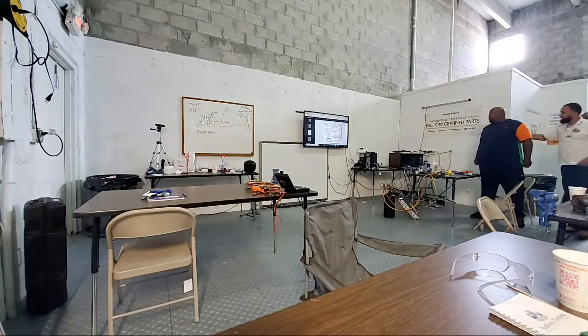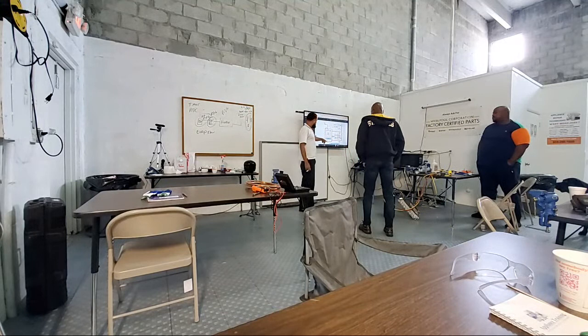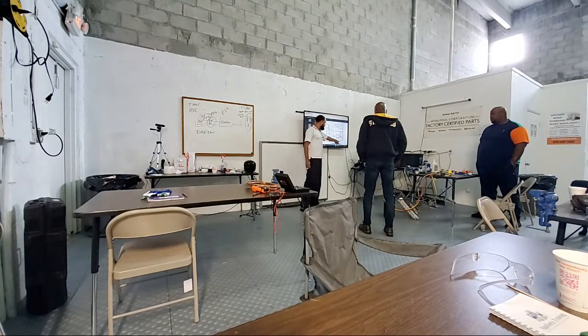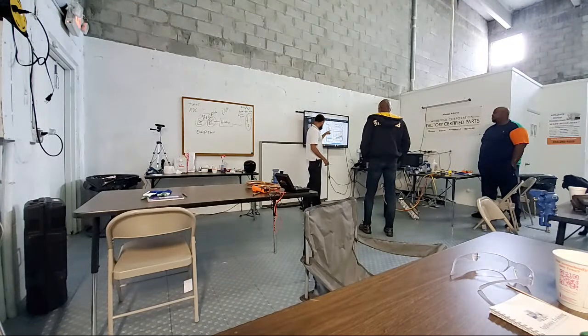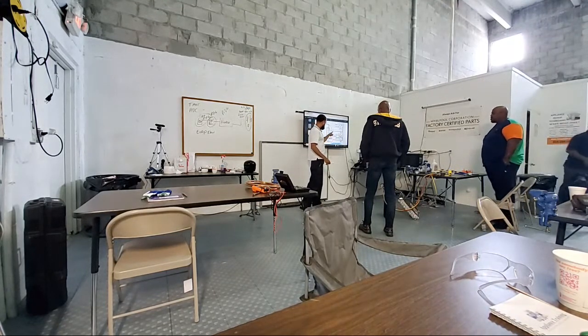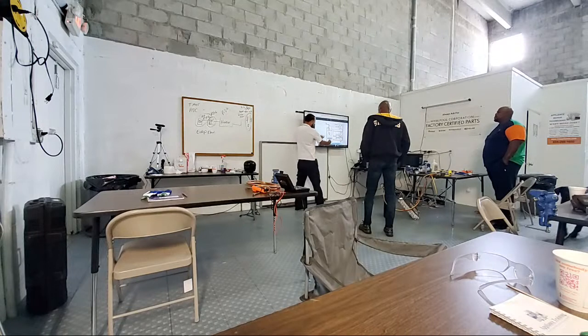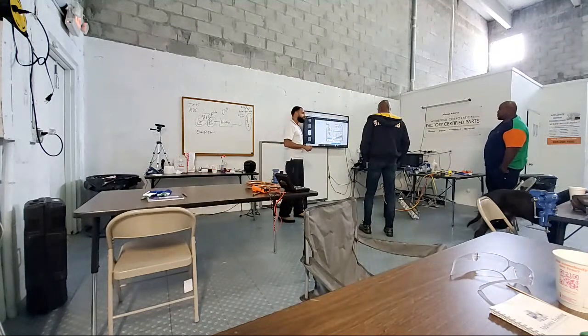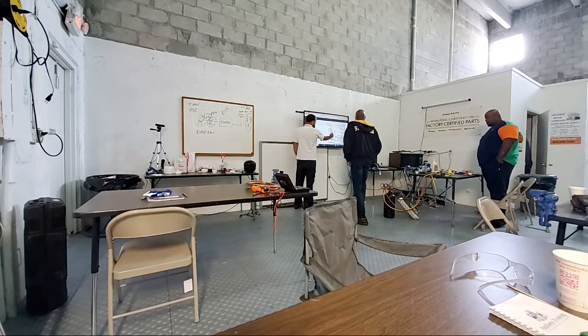When we open it, it closes the thermostat. And what will happen is, come on, take a break, man. What happens now is the thermostat is closed. So now voltage passes through your condenser fan, your compressor, and your evaporator fan. But it has to go back to a neutral. So it comes in through that 6 pin. See? It comes out orange. And then now the neutral comes out. So at the board, you would go 4 to 6. L1 is being provided through here internally.